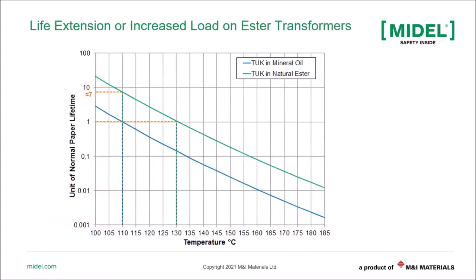So what does that really mean from a practical application in a transformer? What you're seeing here is a chart that's available in the IEEE C57.154 standard. In this chart, there is a temperature range on the x-axis and there's unit life of normal paper on the y-axis. The blue line is what it would be for mineral oil. The green line is what it is for natural ester, but the same line would be applicable to synthetic ester as well. And when a transformer is operating, it's typically operating at 110 degrees C. This is calculated by 65 average winding rise plus 15 degrees C hotspot in the transformer and 30 degrees C ambient. When a transformer is operating under normal condition, it typically has a one unit life in mineral oil if it's made from cellulose material, also known as thermally upgraded kraft material.